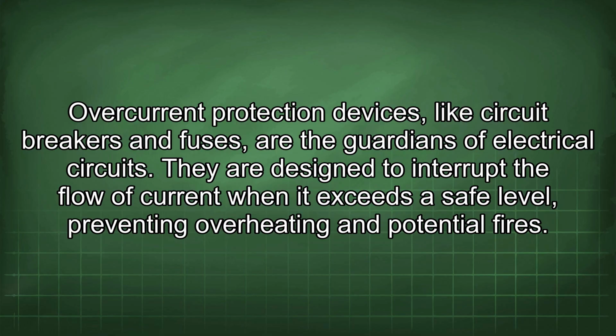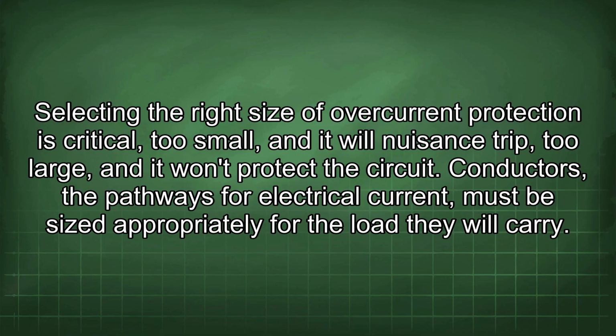Overcurrent protection devices, like circuit breakers and fuses, are the guardians of electrical circuits. They are designed to interrupt the flow of current when it exceeds a safe level, preventing overheating and potential fires. Selecting the right size of overcurrent protection is critical. Too small, and it will nuisance trip. Too large, and it won't protect the circuit.